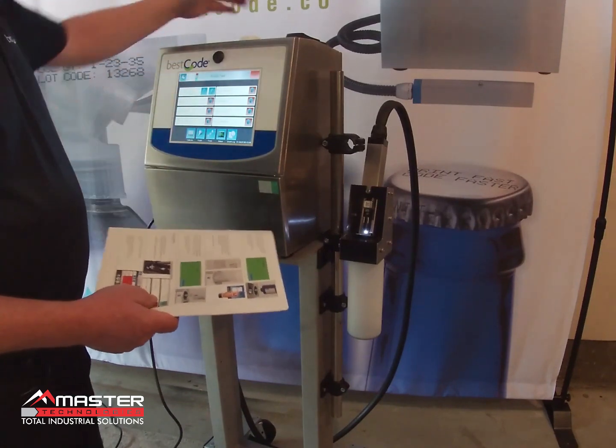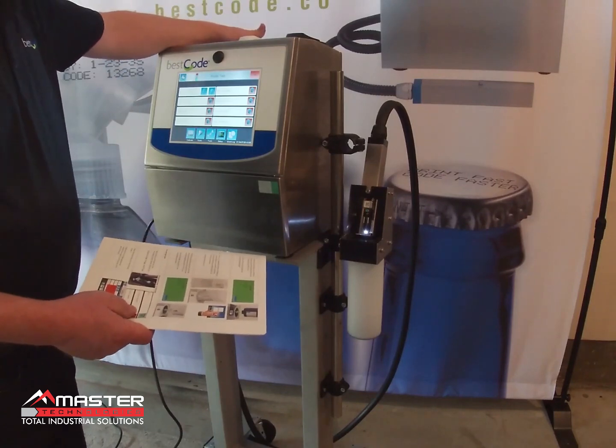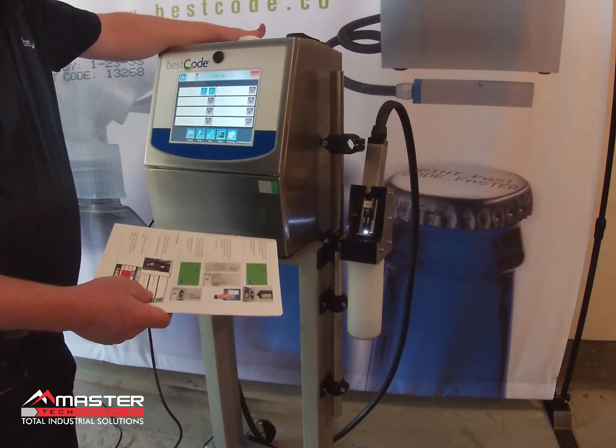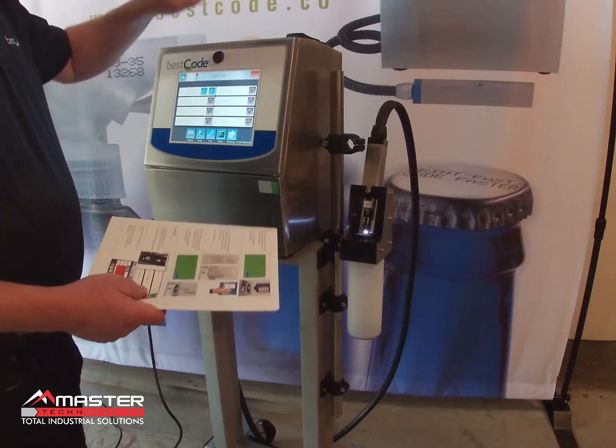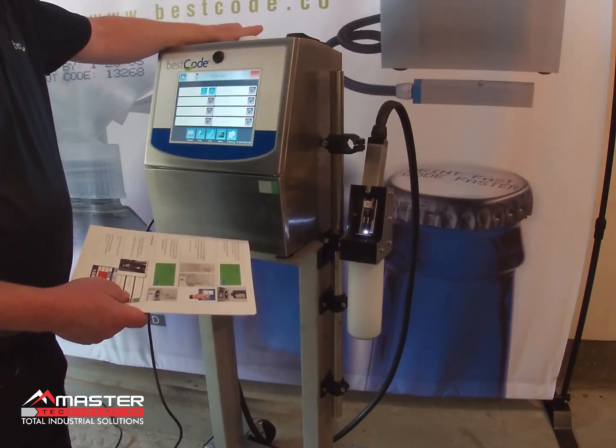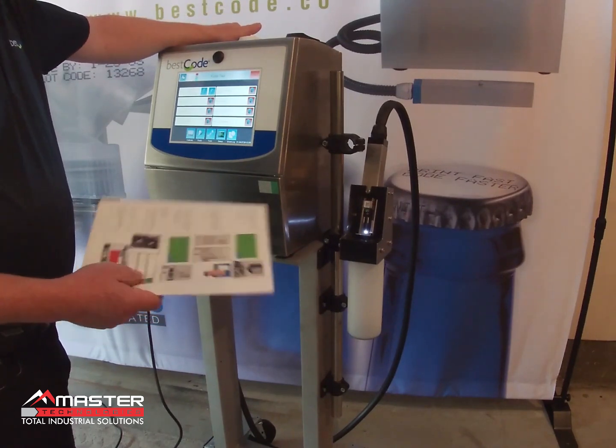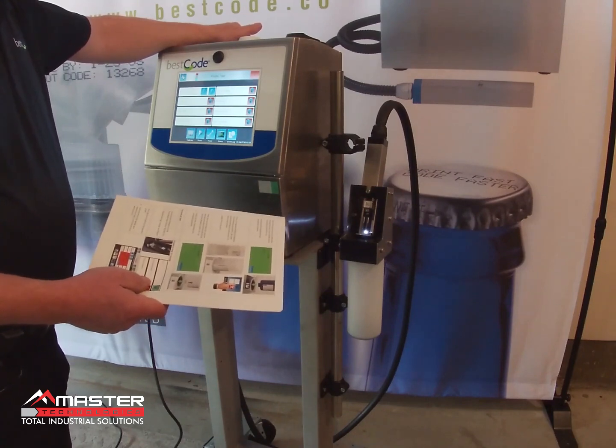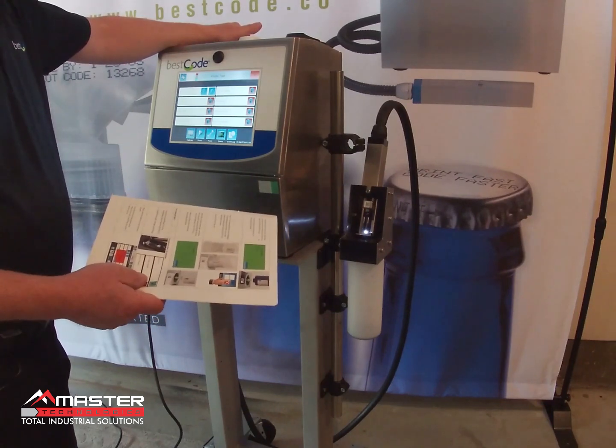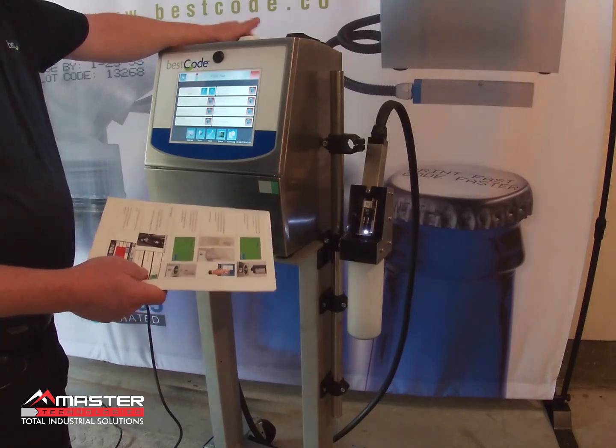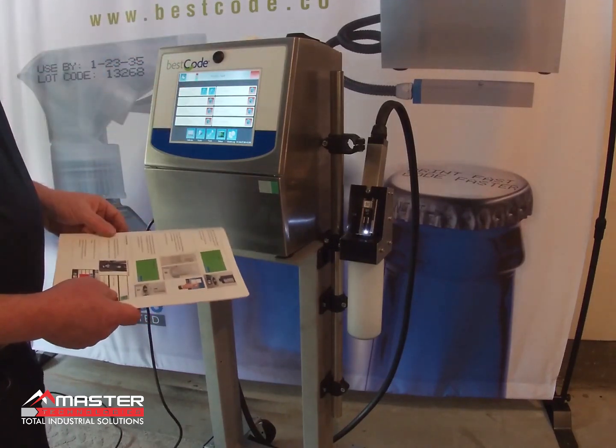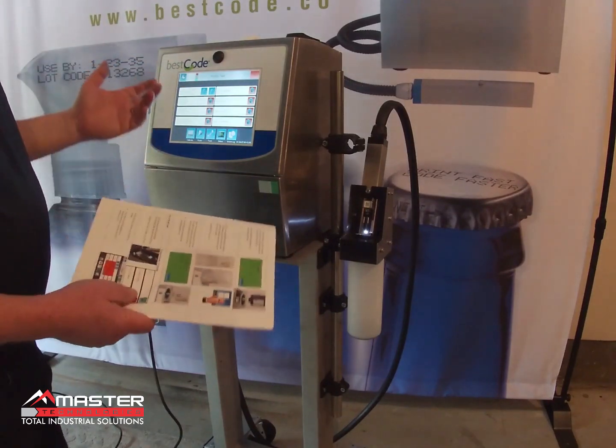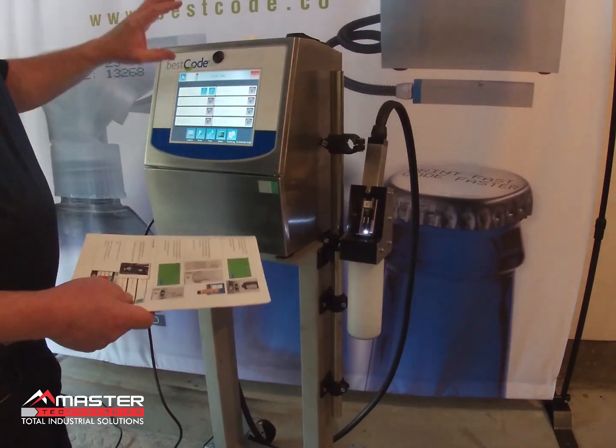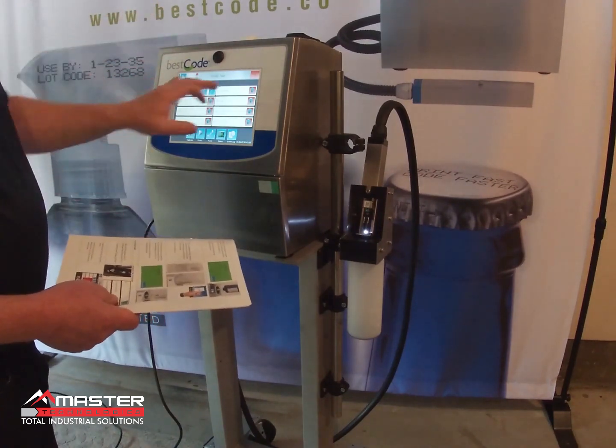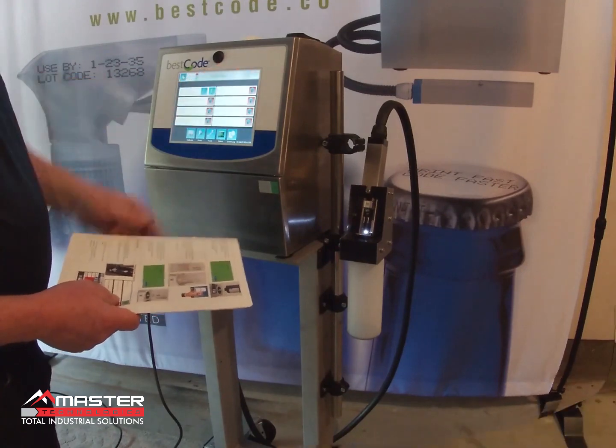So it gives you a chance to open the back up and have a look, make sure there are no leaks, and that you can follow the ink around and it's going everywhere that it should. The other reason is that it eliminates any risk of trapped air in the machine when you do it slowly. So I would leave this on for 5 or 10 minutes, let it fill everything up. Once you've done that, you can go ahead and hit the stop button.